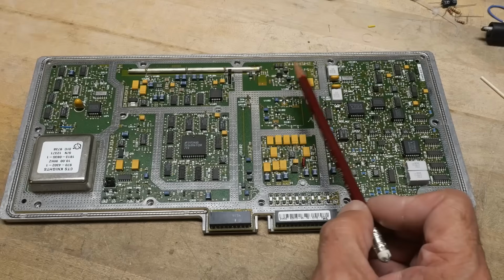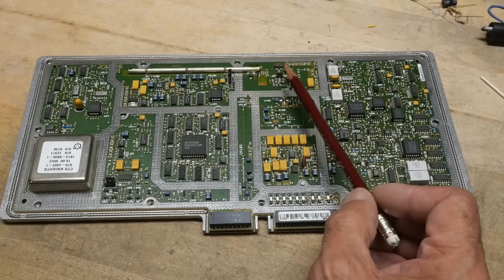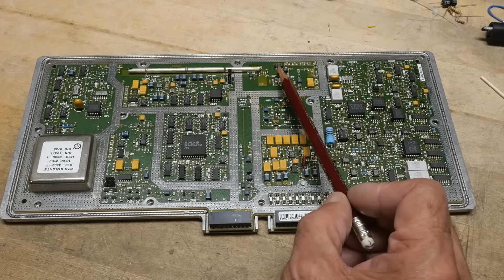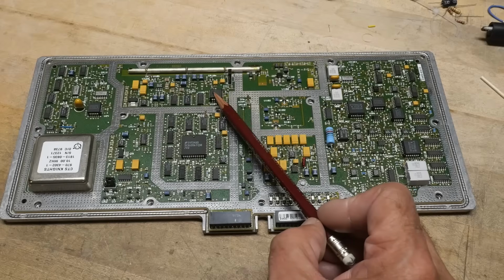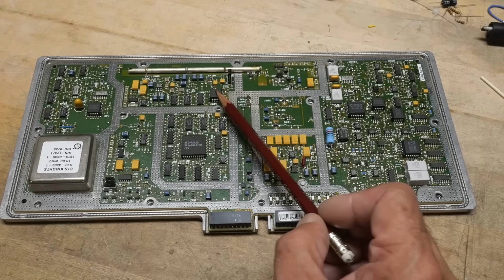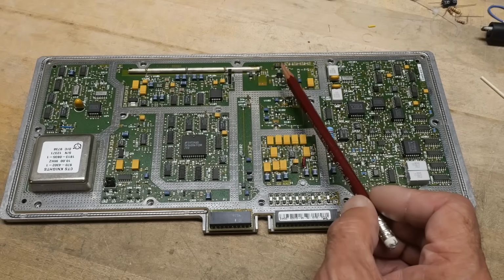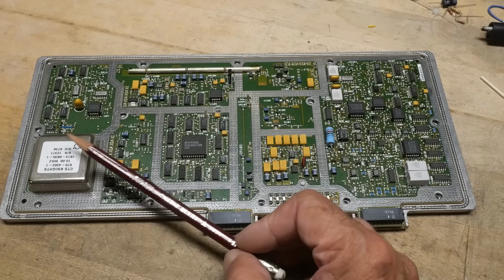The way that it does that is it has a 10 megahertz reference, which is very, very accurate. So it takes the output of this 1 gigahertz oscillator, it runs it into a gate array, which is this right here, divides it by 100. So it takes the 1 gigahertz, divides it by 100, it gets 10 megahertz. So we have 10 megahertz and 10 megahertz that goes into a phase lock loop, and then we can phase lock this to exactly the phase relationship to this 10 megahertz over here, and we have a very accurate 1 gigahertz.